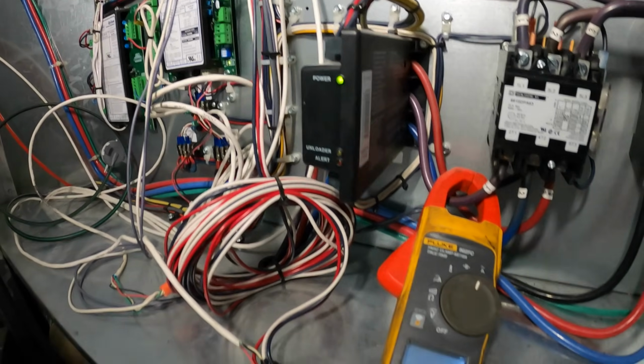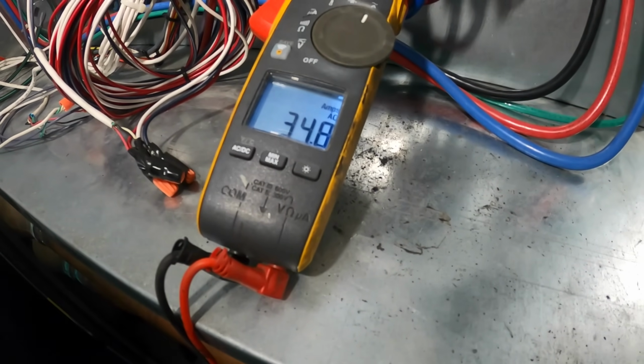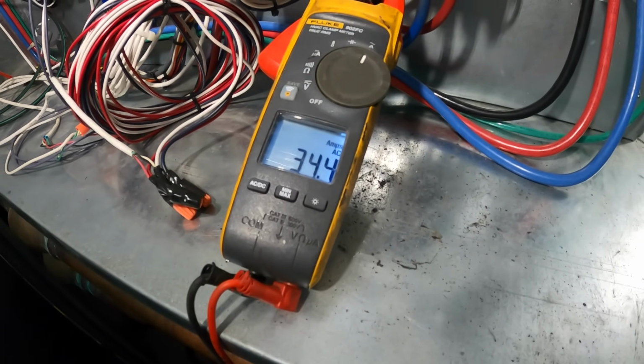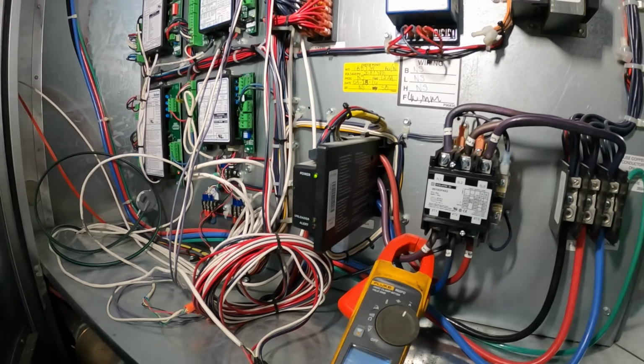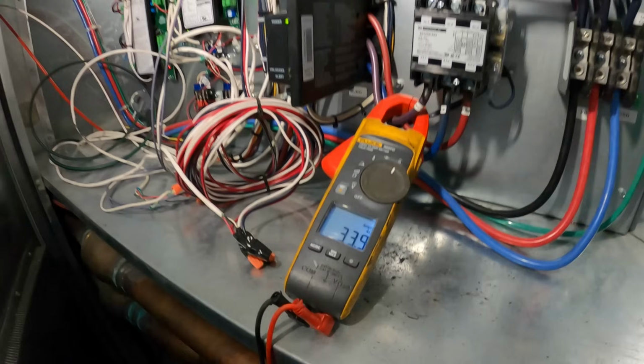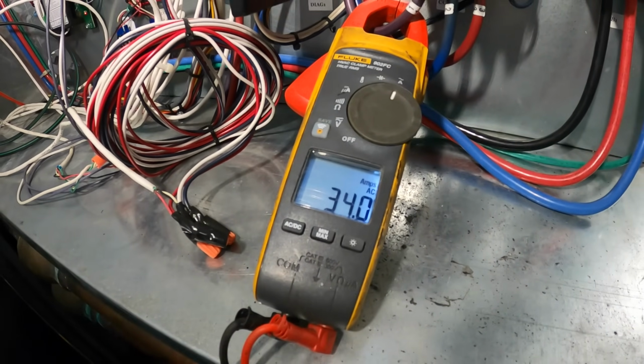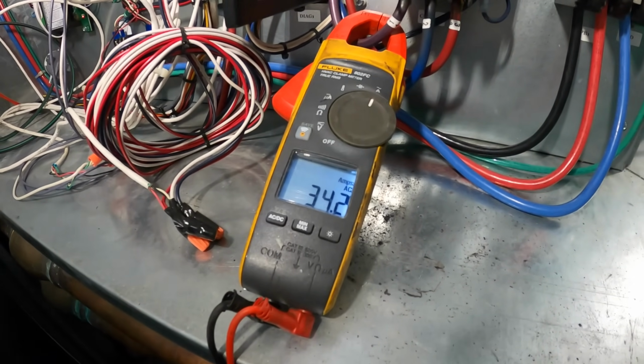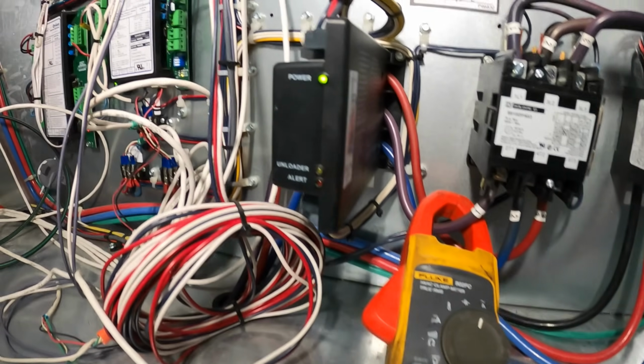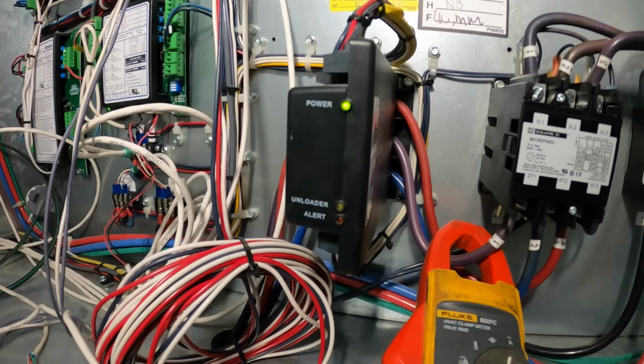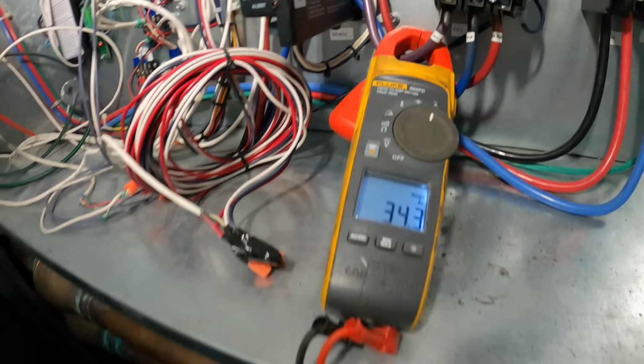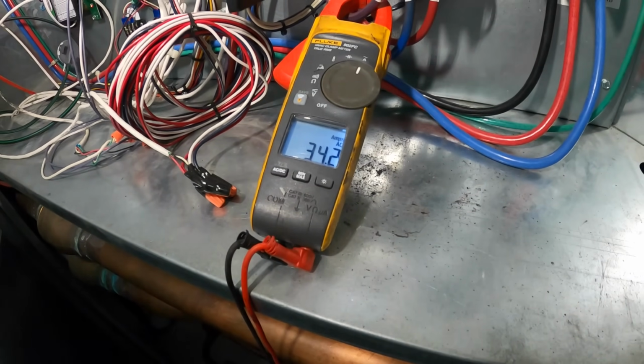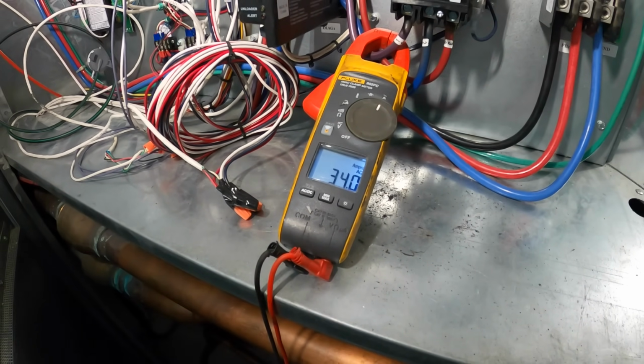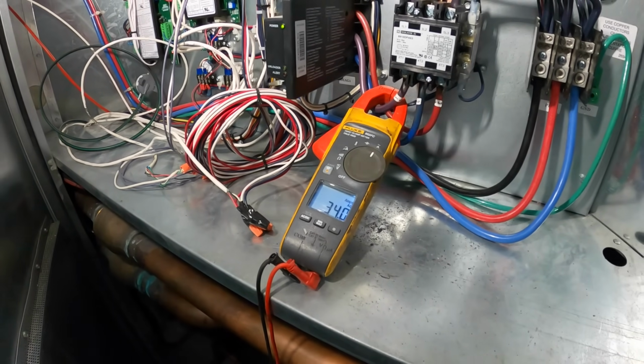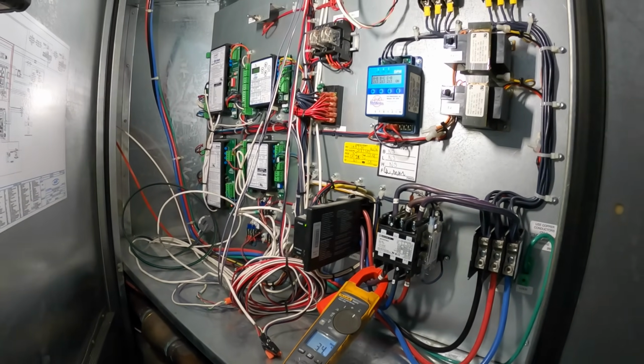So this thing loads and unloads. So right now, this thing is at full capacity with this amperage. Then if it has been off for a while, the space is warm, so if anything, it's not gonna unload. So we're at full capacity right now. When the green light for unloader comes on, you'll see the amperage go less, and I guess that's a way for it to go with efficiency. But there we go, guys. We are running.